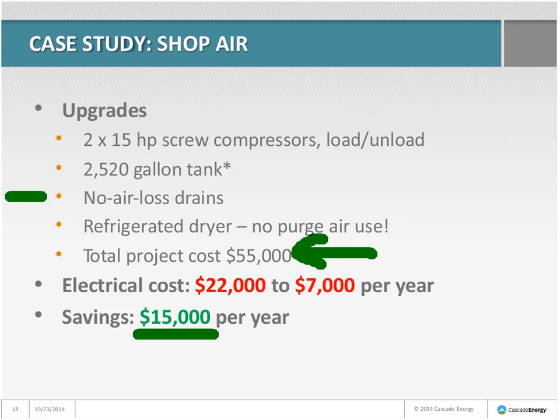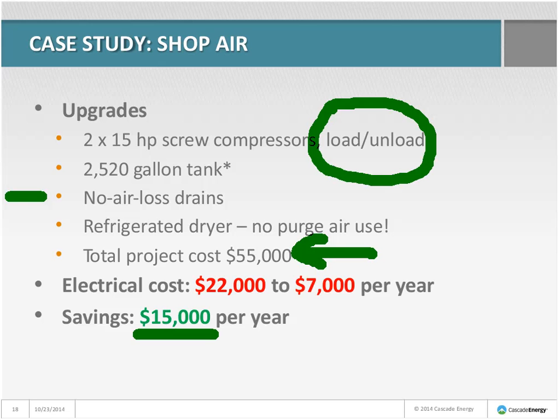These guys could have simply cleaned up the existing equipment — used load-unload control on the big 75-horse compressor and added purge controls to the desiccant dryer. But they decided this equipment was oversized, mismatched, and the wrong type of dryer, so they started over. Their air use was all indoors in a shop that never got below 50 degrees in winter, so they didn't need super-dry minus-40 dew point compressed air — the refrigerated dryer saved them a bunch of purge air consumption.